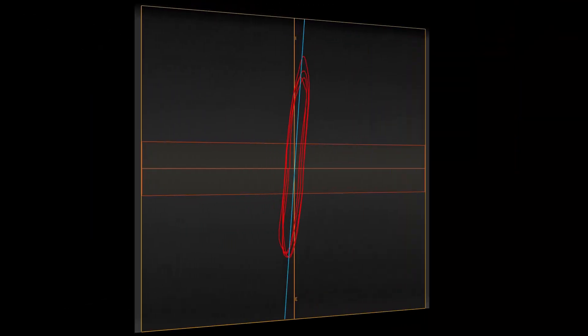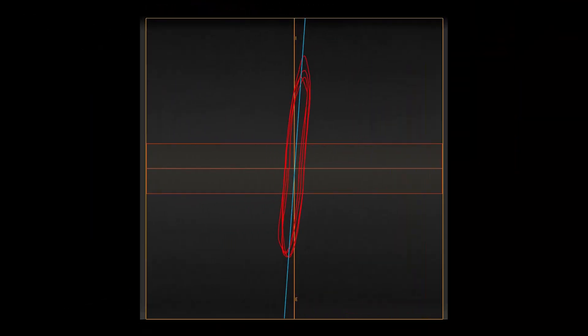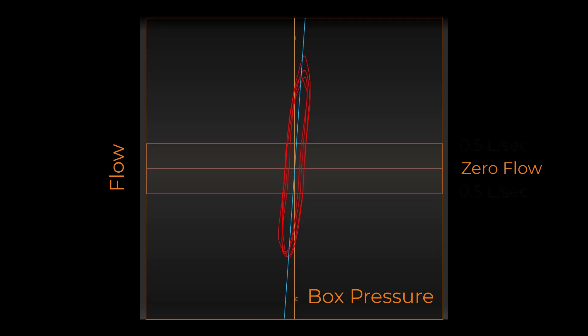The red or open shutter tracing is slightly different than the closed shutter loop. While the blue tracing represents mouth pressure over box pressure, the open shutter trace represents flow over box pressure. The middle horizontal line represents zero flow, while the upper and lower horizontal lines indicate plus and minus 0.5 liters per second flow.